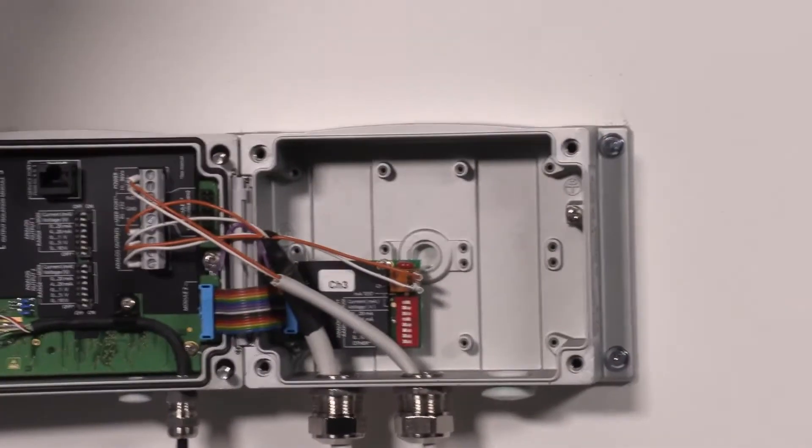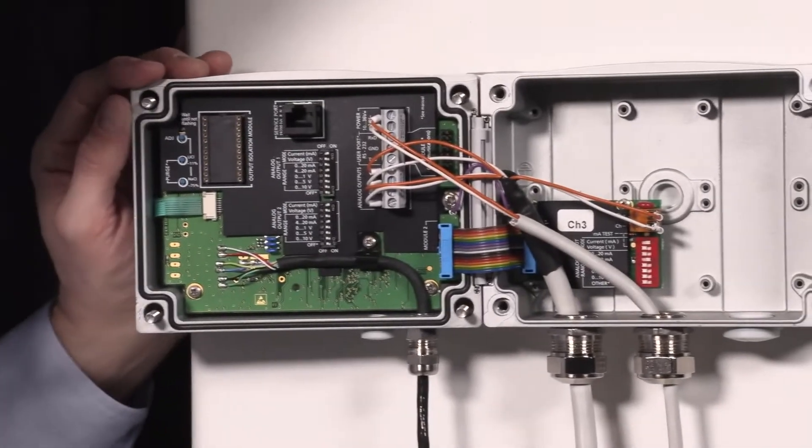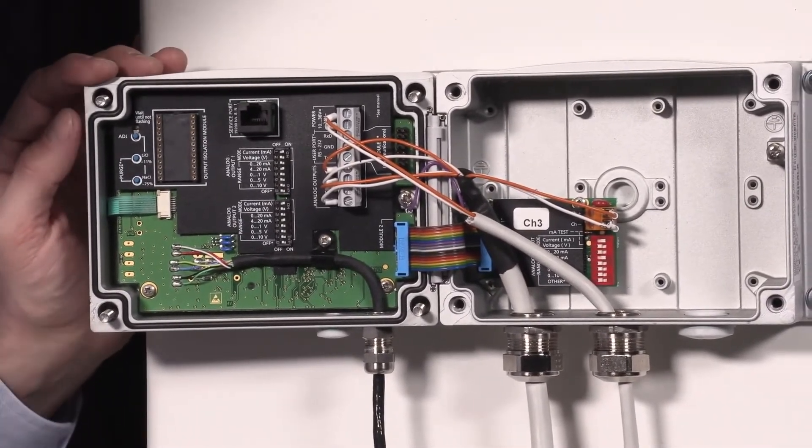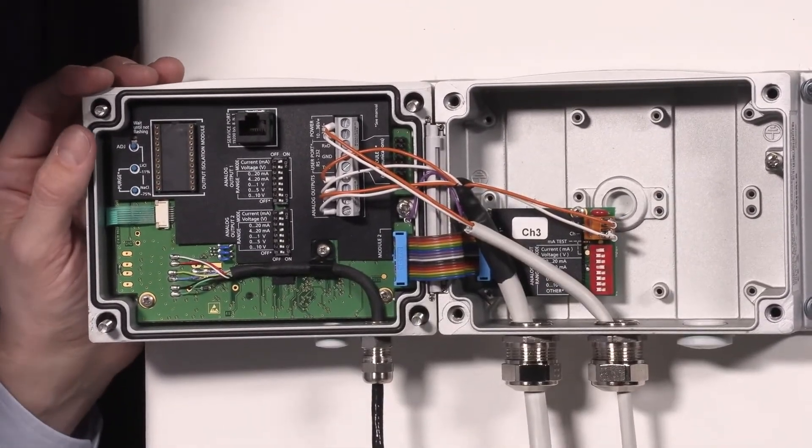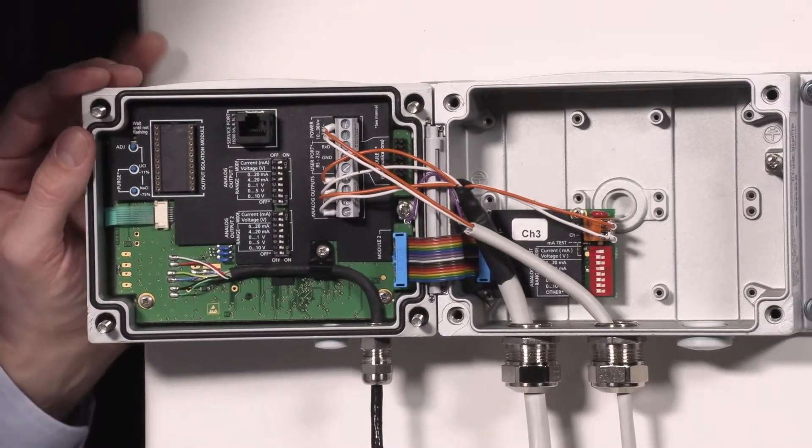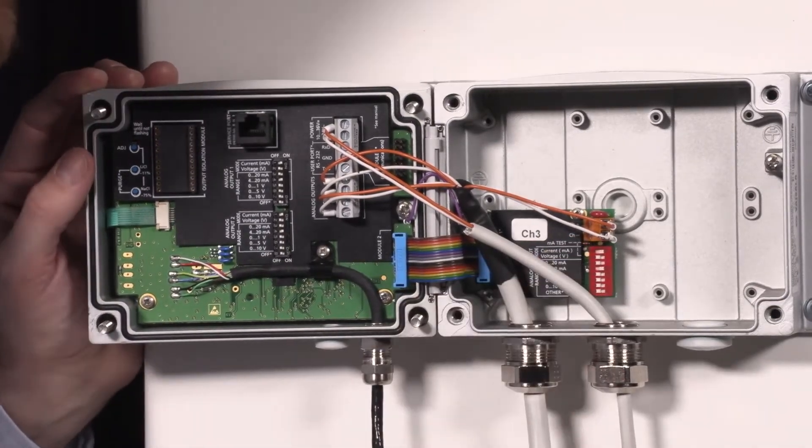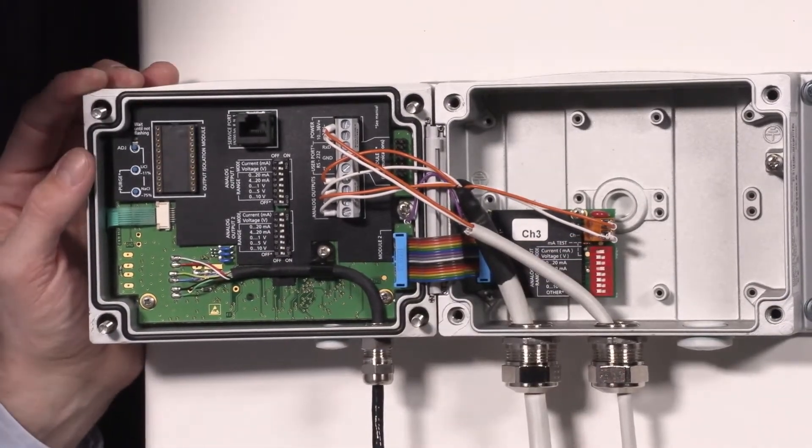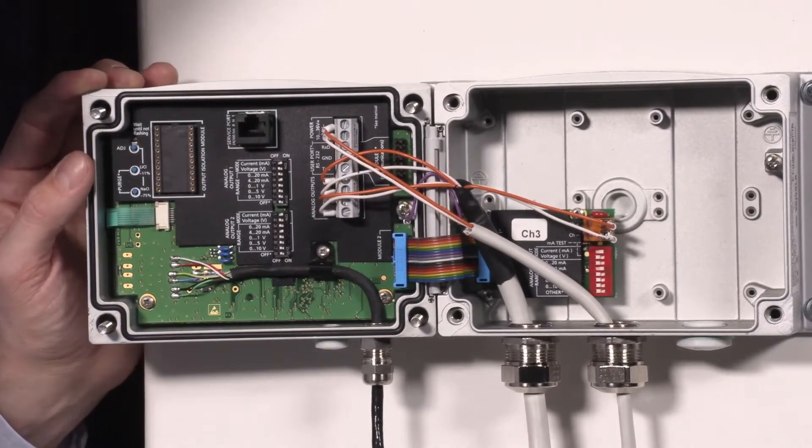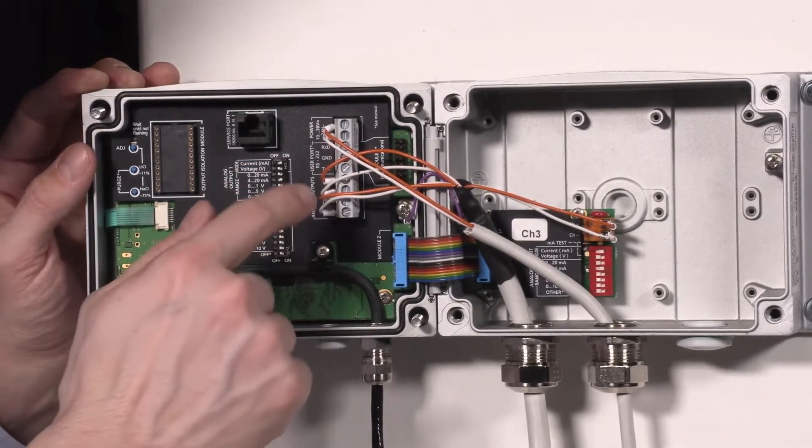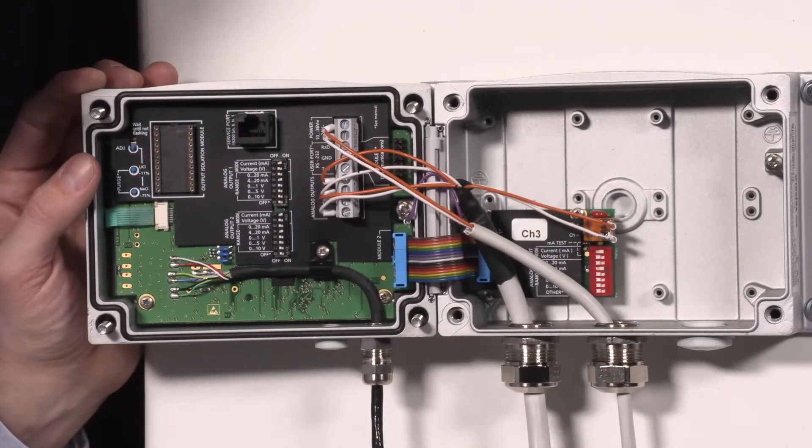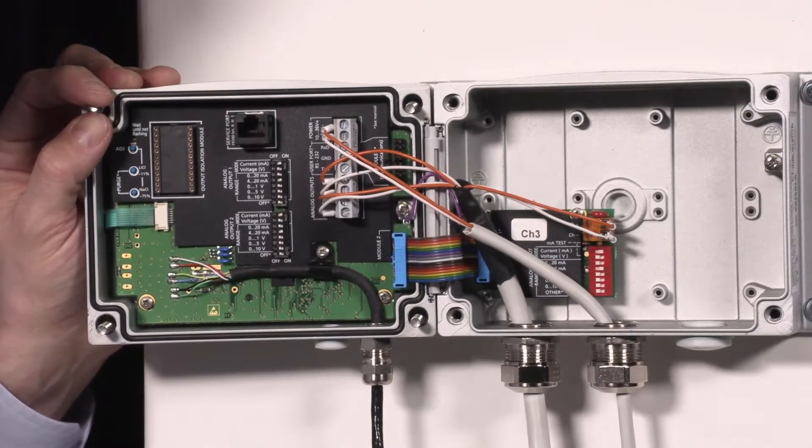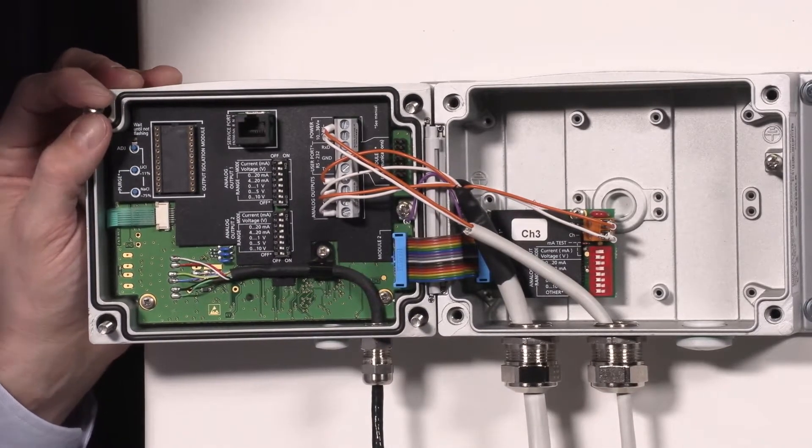The lid is open and we can see different types of modules in the HMT-330. In this model, we have an extra analog output channel 3, so we have relative humidity, temperature, and this extra output is outputting dew point temperature.